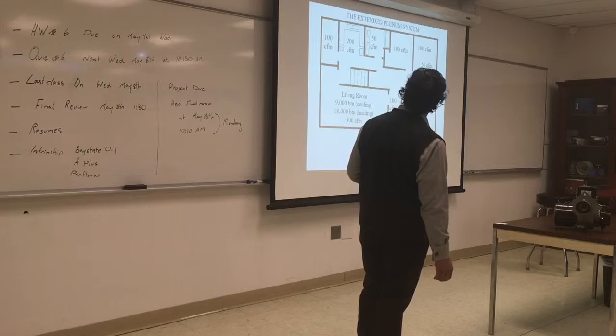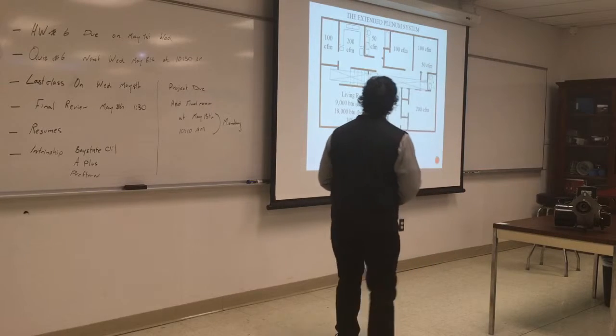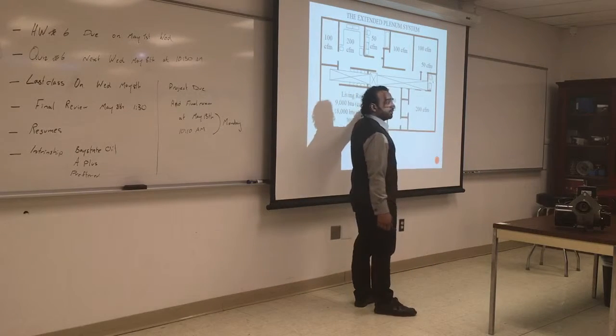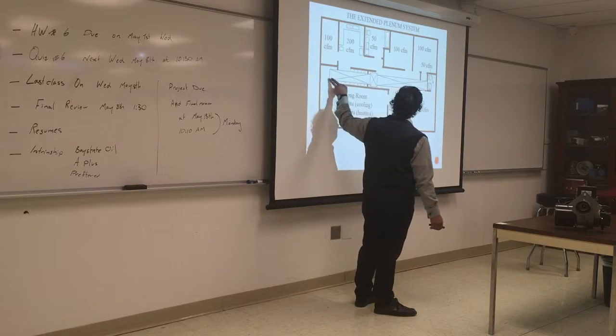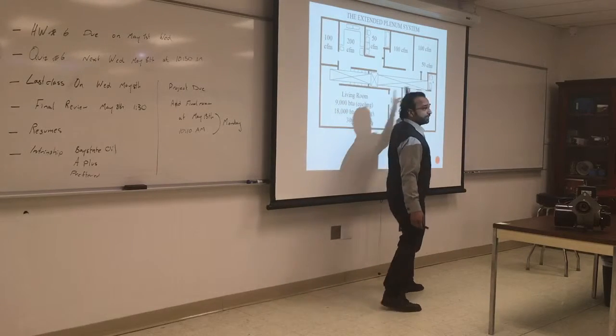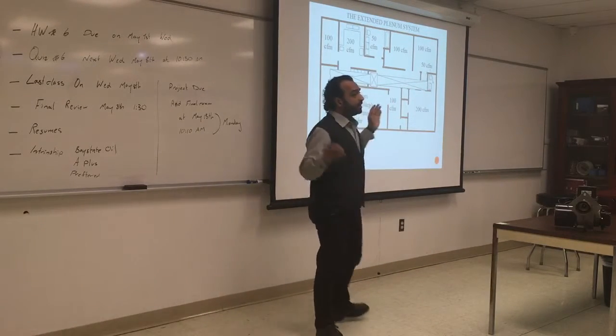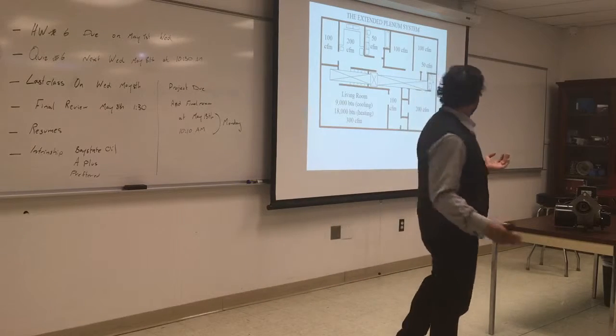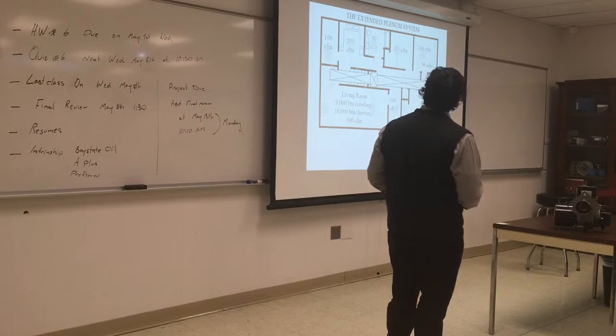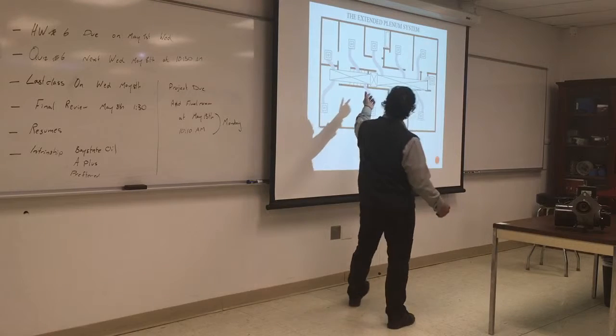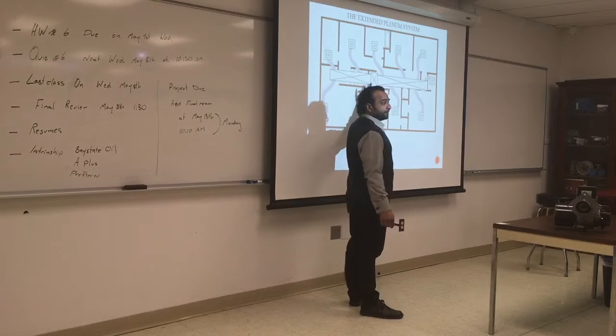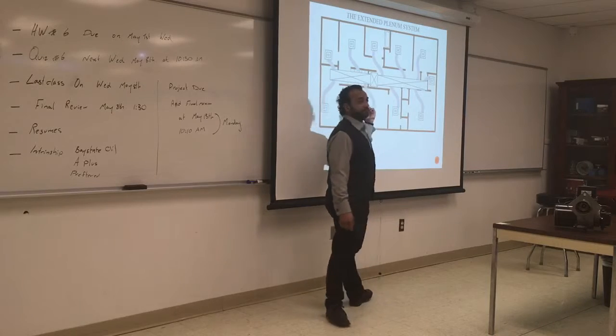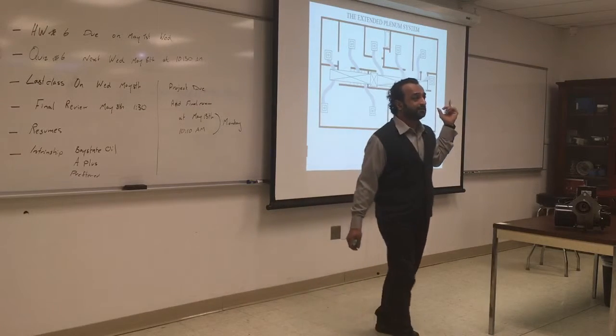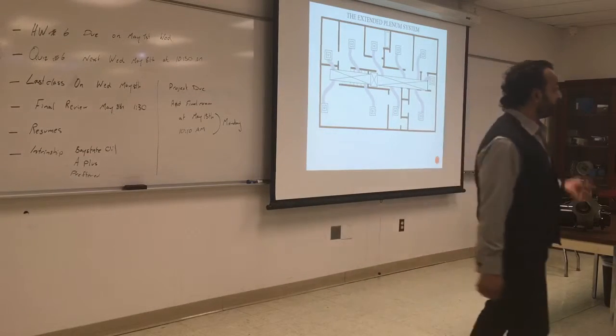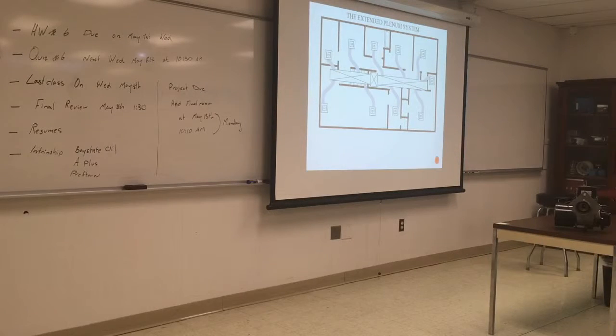So if we have a picture here, yeah, this is our plenum. So our heating unit goes both ways, extended all the way to the end. And that's going to be uniform temperature and uniform pressure. And from that, you supply little branches or flexible duct. I'm not a big fan of flexible duct if it's longer than 6 feet, because again, there's a lot of loss due to friction, because it has a lot of ridges.